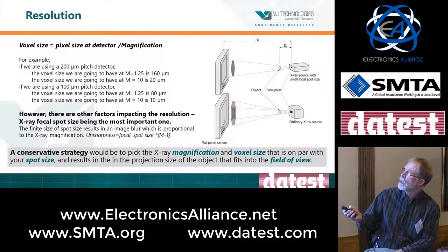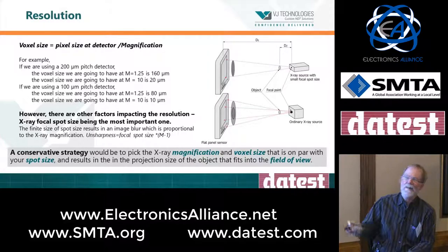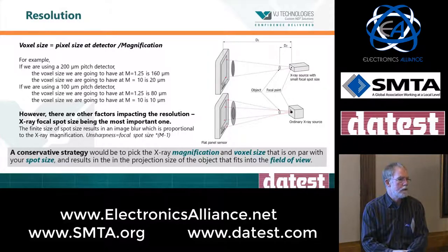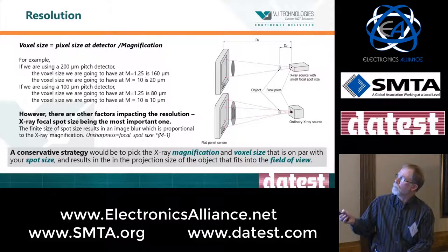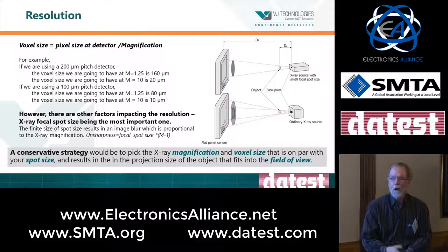It's all a function of the positioning of the object relative to the source and relative to the detector. And this has a big impact on the technique development I was talking about at the beginning. Often we have to play around with this, and what we have to tell the customer is, we don't know what's going to create the best exposure and the best image for you. Give us some time. Let us take a couple of different shots. Let us show you what we can do, and let us see if we can achieve and capture the defect you're looking to find. And then from that, we optimize the process, typically to make it suitable for production after that.